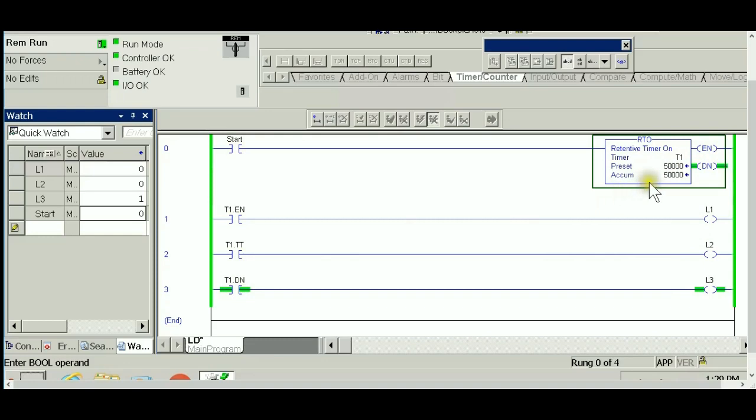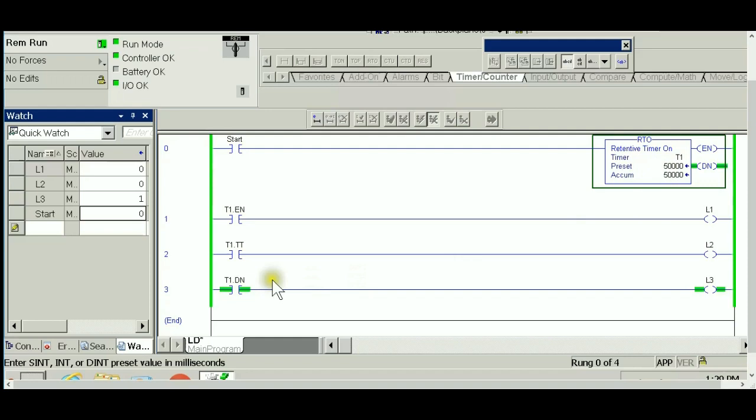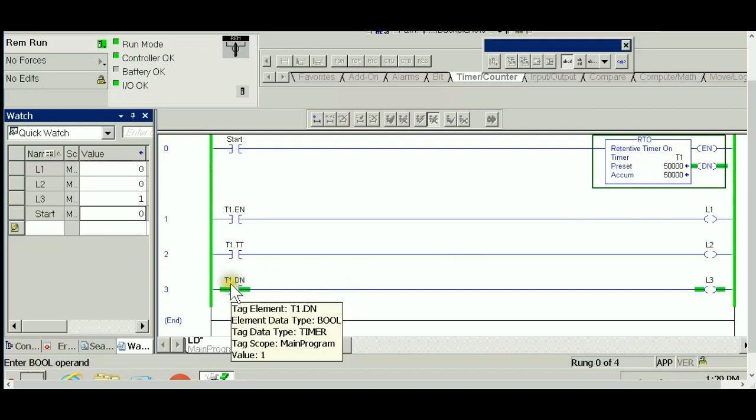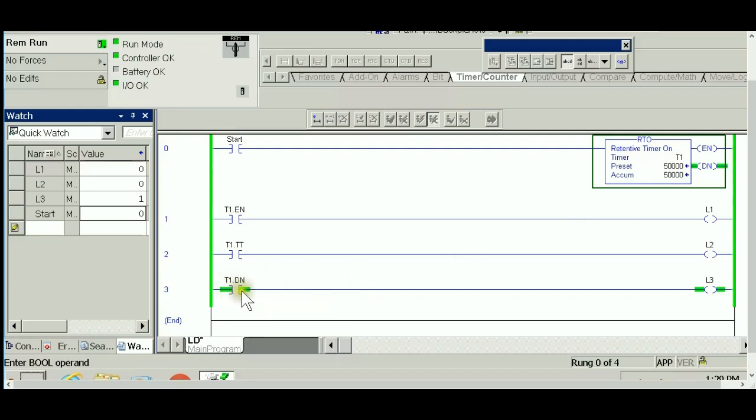However, the done bit always looks at the accumulator. As long as the accumulator is equal to the preset value, there is no reason for the done bit not to remain set. This behavior is what makes the RTO different from the TON timer. Please remember this.